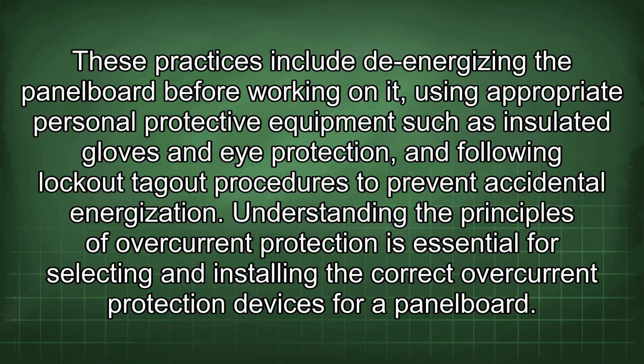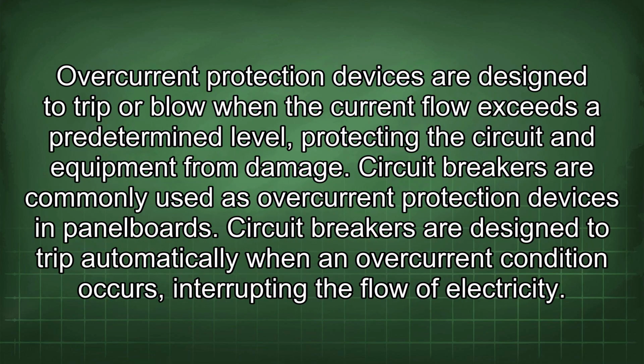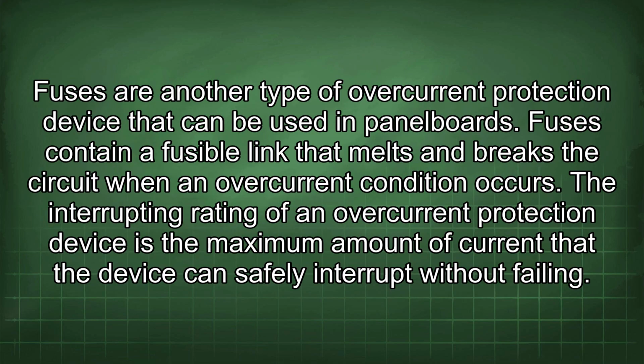Understanding the principles of overcurrent protection is essential for selecting and installing the correct overcurrent protection devices for a panelboard. Overcurrent protection devices are designed to trip or blow when the current flow exceeds a predetermined level, protecting the circuit and equipment from damage. Circuit breakers are commonly used as overcurrent protection devices in panelboards. Circuit breakers are designed to trip automatically when an overcurrent condition occurs, interrupting the flow of electricity. Fuses are another type of overcurrent protection device that can be used in panelboards. Fuses contain a fusible link that melts and breaks the circuit when an overcurrent condition occurs.